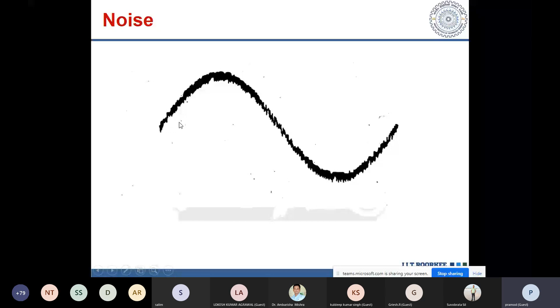Now, if you consider conventional devices like the transformer, the transformer draws basically a magnetizing current. And the characteristic of the transformer is like this, the magnetizing characteristic. It is not a linear one. It operates somewhere here. And because of this, since the voltage applied is sinusoidal, the flux in the transformer should be sinusoidal. And to have a sinusoidal flux, the current should be of this nature, which is having a dominant third harmonic.